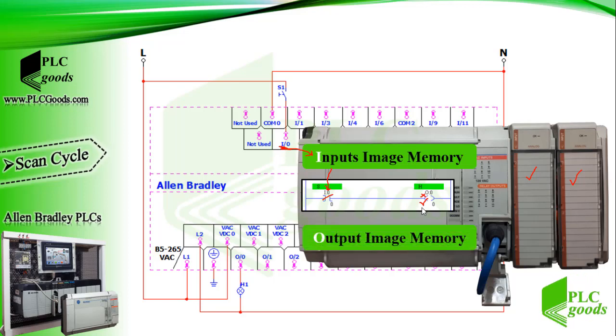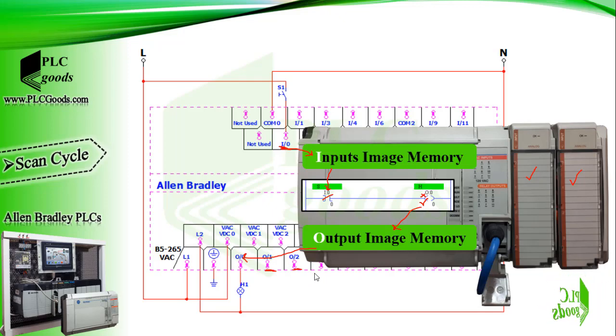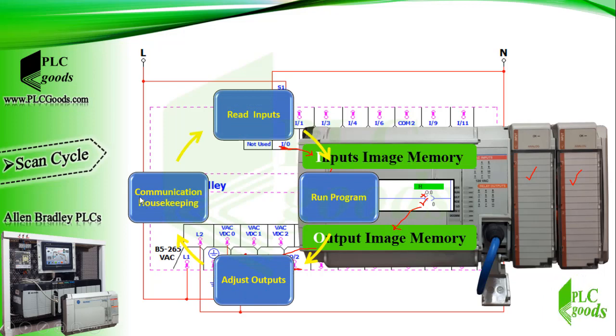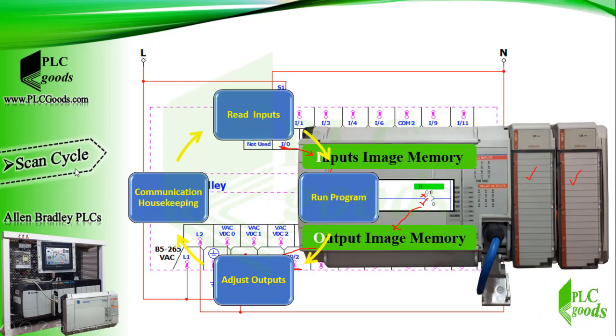During program execution, the processor does not change its real outputs. Instead, it updates the output image memory based on the solution of the user logic program. When the PLC processor reaches the end of the user program, it activates or deactivates all its real outputs according to the output image memory. After this, the PLC does housekeeping and communication tasks, then reads all input statuses again. This cycle is called the scan cycle, which takes about five to ten milliseconds depending on the processor type and program size.